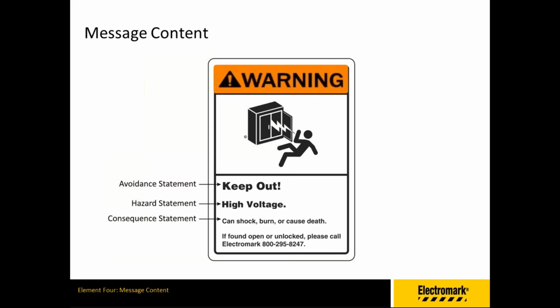On the other hand, a hazard message on the outside of a cabinet intended to warn the general public should contain all three word message components, since that audience can obviously access that physical environment and they would not be expected to be knowledgeable of the hazards that it contains.